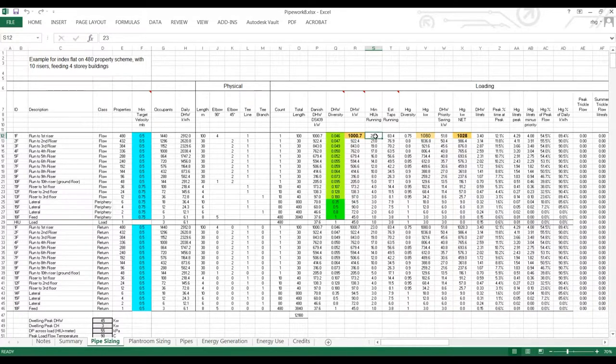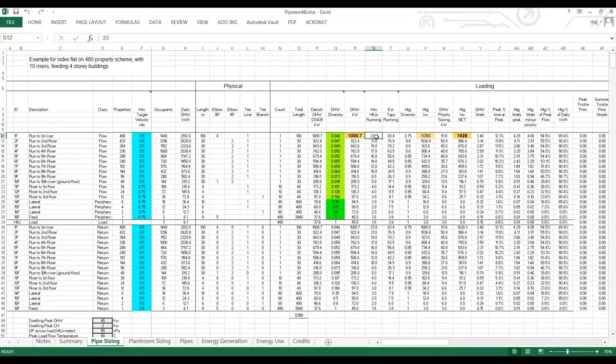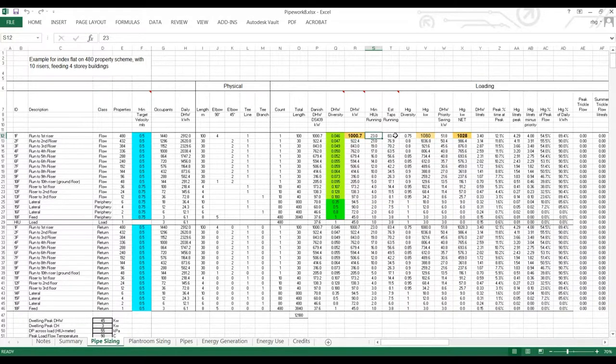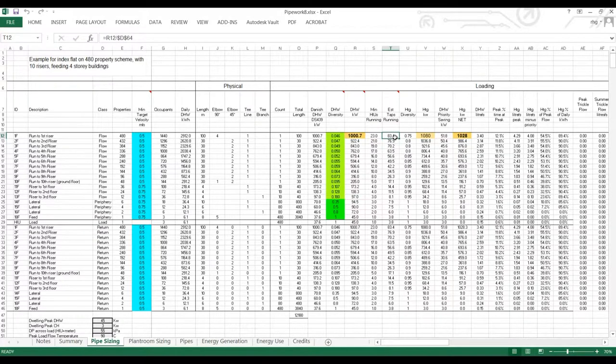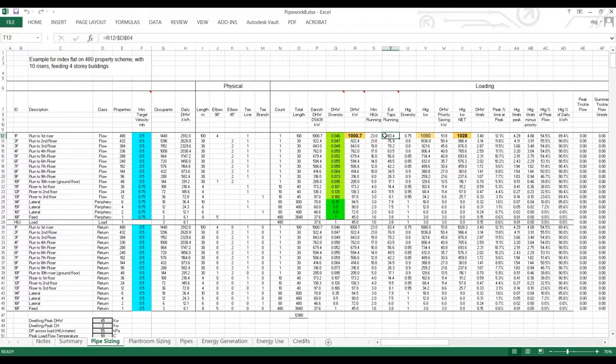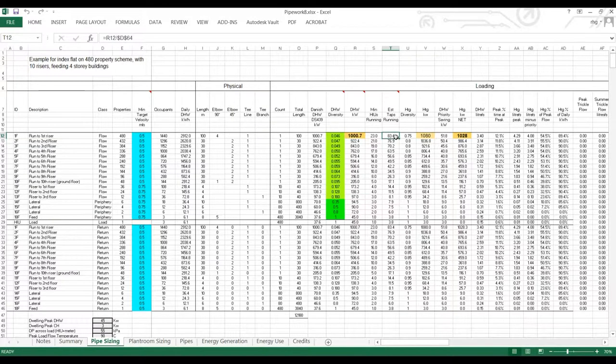So while these HIUs are running to deliver this load, they'll be the same number of HIUs turning off their central heating load. We have an estimate of the number of taps running. So this isn't used in any calculations, but it's the average load divided by this one, just to give us a feel for how many taps may be running at full load.